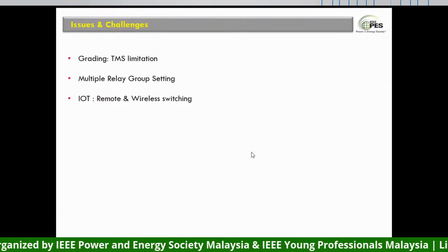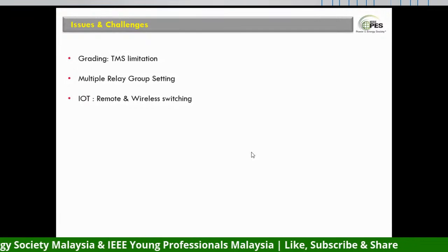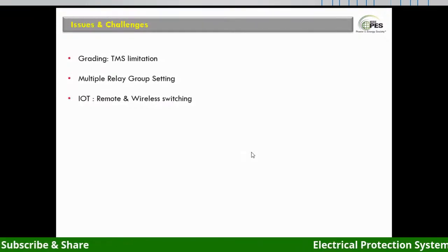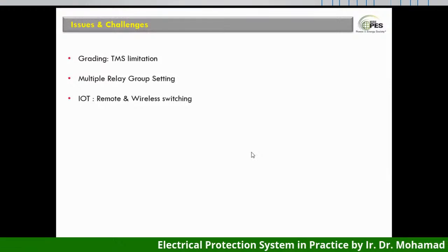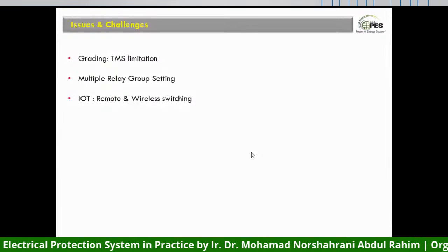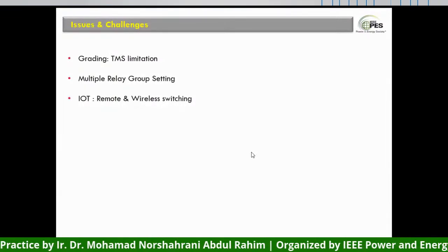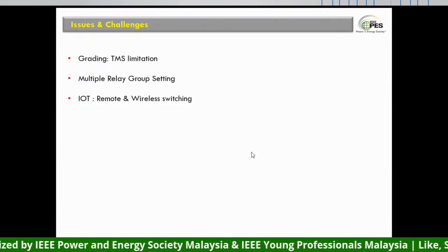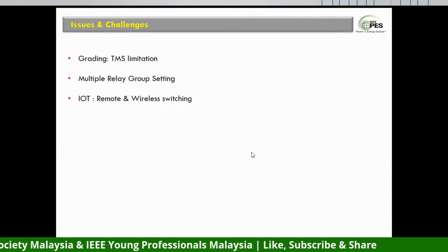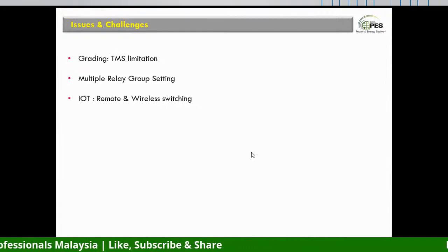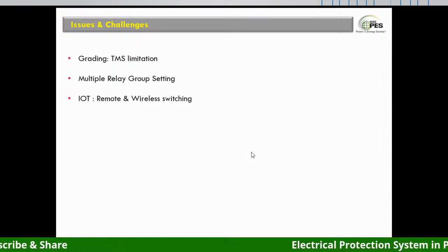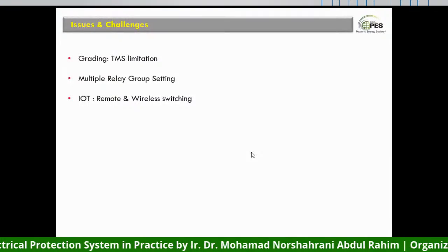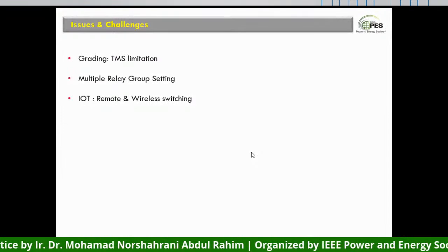Basically the industry and manufacturers are promoting the use of remote and wireless switching. But on the practical side, especially on maintenance, we need to consider whether our people have the integrity to use this system. I have my experience. We were installing a protection system for upgrading hospitals. We tried the wireless switching, but even though the technology is there, we only used it during the T&C. Upon handing over, we didn't set the wireless function because of operational issues and safety issues.